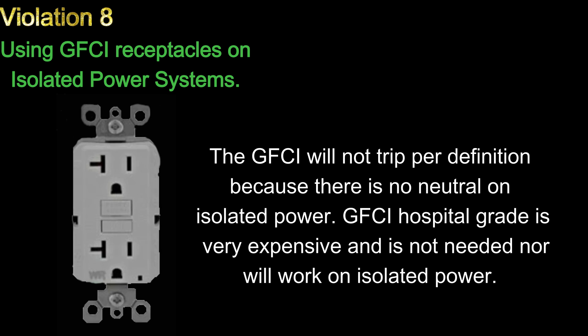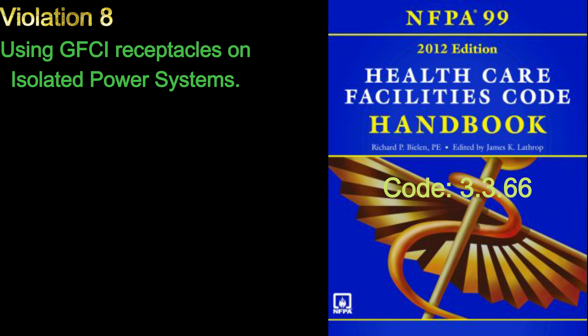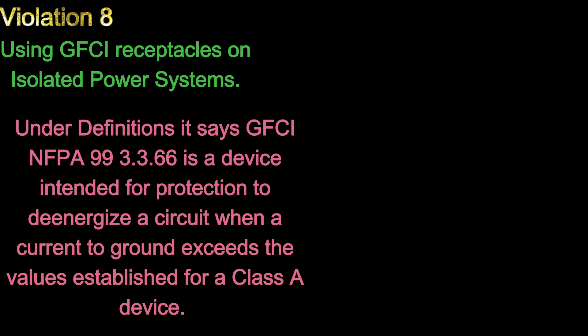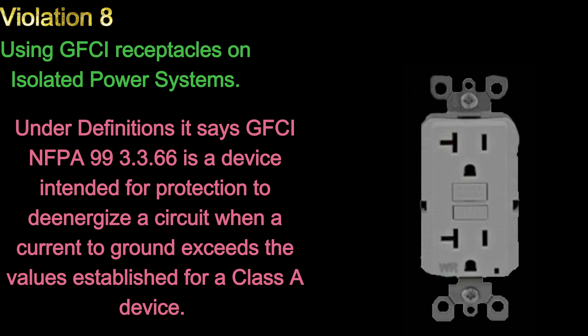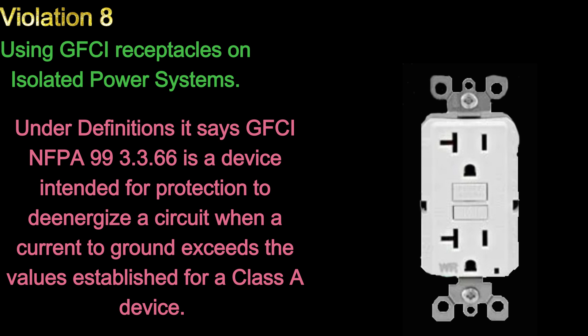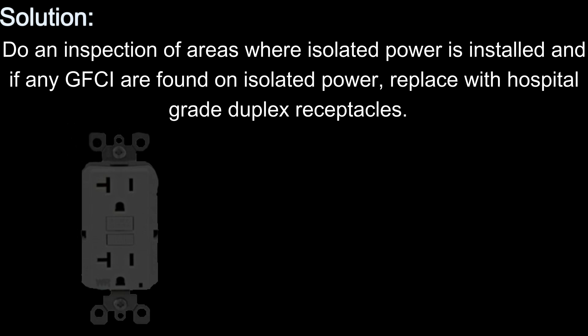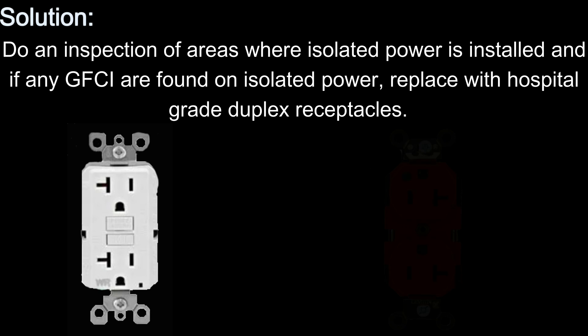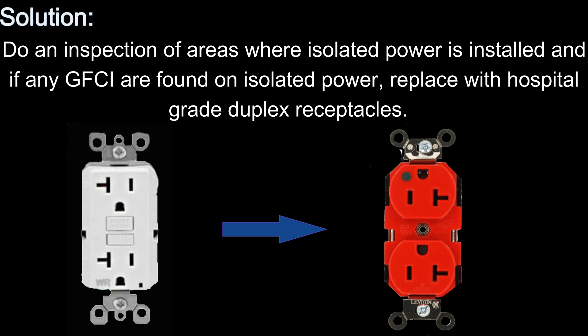Number 8: Using GFCI receptacles on isolated power systems. The GFCI will not trip per definition because there is no neutral on isolated power. GFCI hospital grade is very expensive and is not needed nor does it work on isolated power. Code 3.3.66 — under definitions, NFPA 99 3.3.66 states a GFCI is a device intended for protection to de-energize a circuit when a current to ground exceeds the values established for a class A device. Solution: Do an inspection of areas where isolated power is installed, and if any GFCI receptacles are found on isolated power, replace them with hospital grade duplex receptacles.